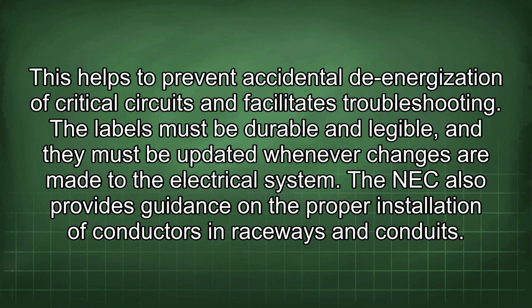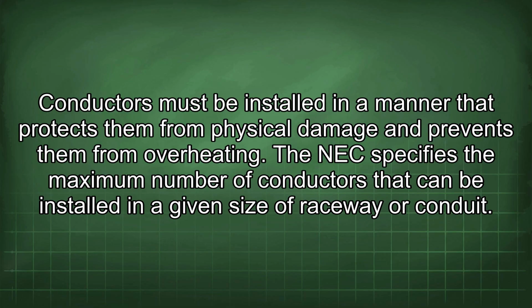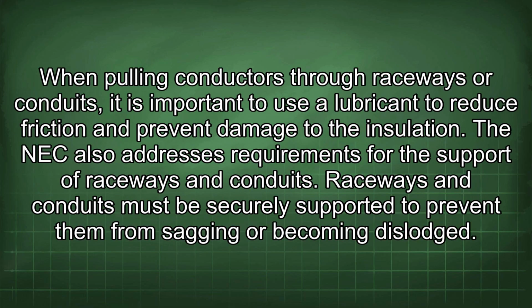The NEC also provides guidance on the proper installation of conductors in raceways and conduits. Conductors must be installed in a manner that protects them from physical damage and prevents them from overheating. The NEC specifies the maximum number of conductors that can be installed in a given size of raceway or conduit. When pulling conductors through raceways or conduits, it is important to use a lubricant to reduce friction and prevent damage to the insulation. The NEC also addresses requirements for the support of raceways and conduits.